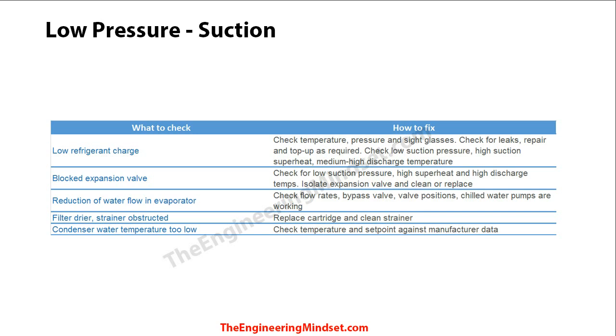Low suction pressure could also be caused by reduced water flow into the evaporator, so check all valves, bypass valves, and pumps. Refer to commissioning data if you're unsure of the correct flow rate. Also check the filter dryer and strainer for blockages, and clean or replace them as needed. The condenser water temperature being too low can also cause this — adjust bypass valves around the cooling towers to ensure water returns at the correct temperature.